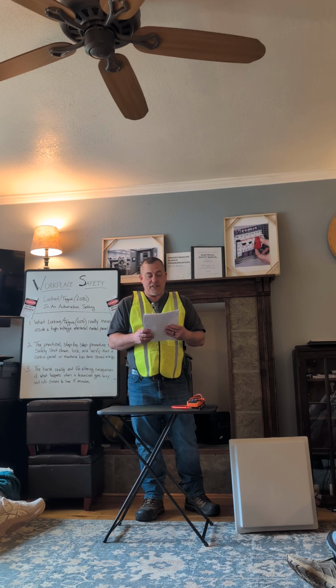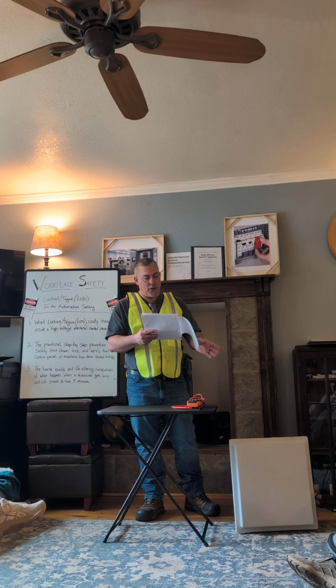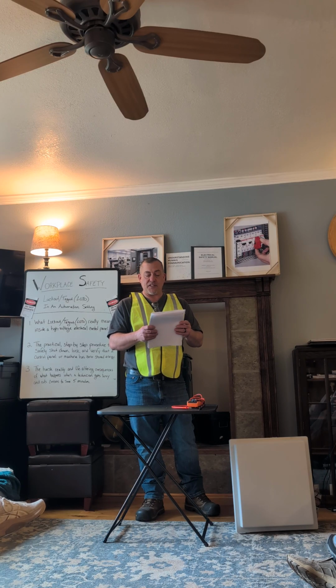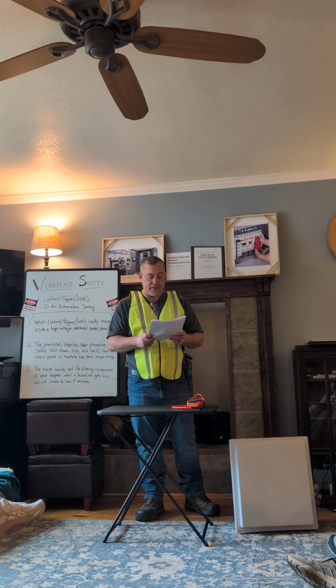Now that we understand the types of dangerous energy, let's walk through the exact steps to secure a machine using lockout-tagout. The standard lockout-tagout safety protocol consists of 8 crucial steps designed to ensure electrical equipment is completely de-energized before any work or maintenance begins.